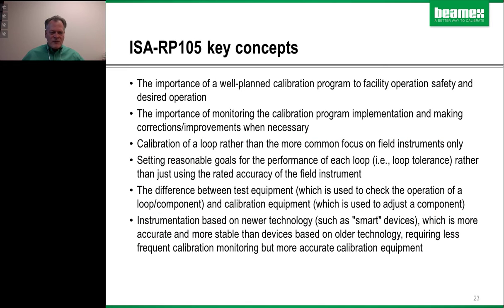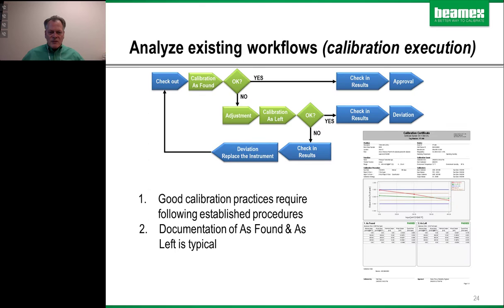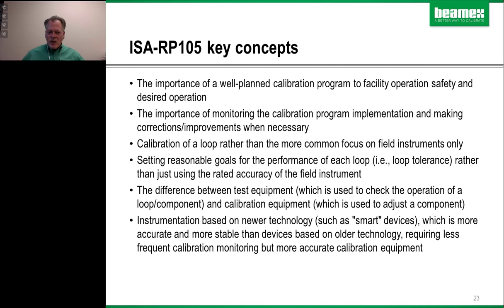I'm not going to read all these off to you, but here's a bullet list of some things that you should consider in your calibration program, and look for ways to become more efficient and do things more accurately and with better efficiency. So, ideas of looking at a loop rather than individual instruments, and leveraging your smart devices, which are much different than the old pneumatic devices. Don't use an old pneumatic type approach to a smart instrument.